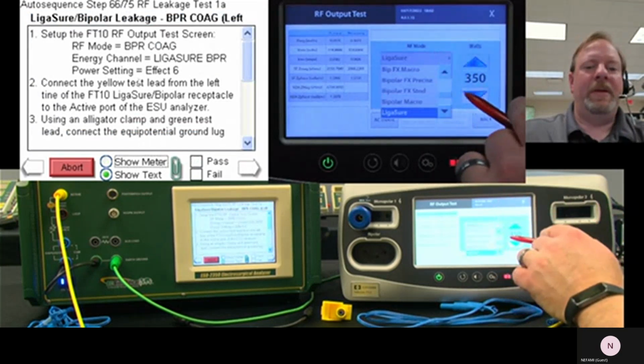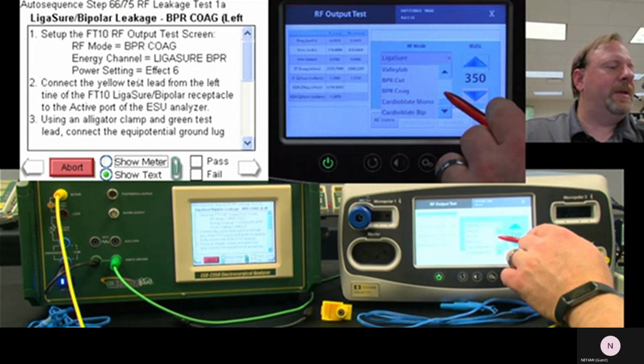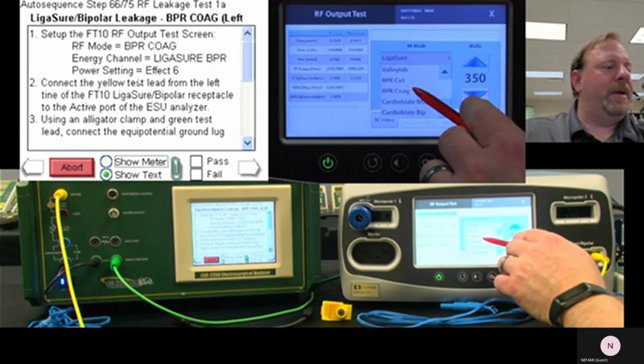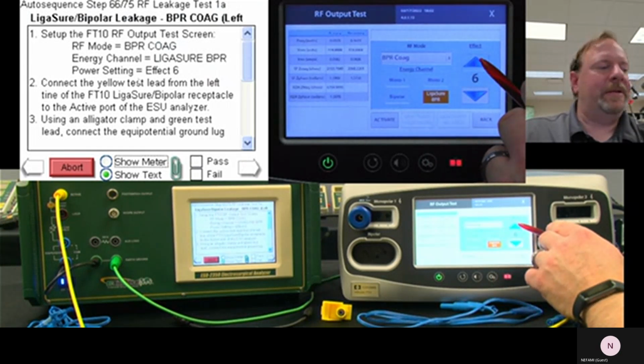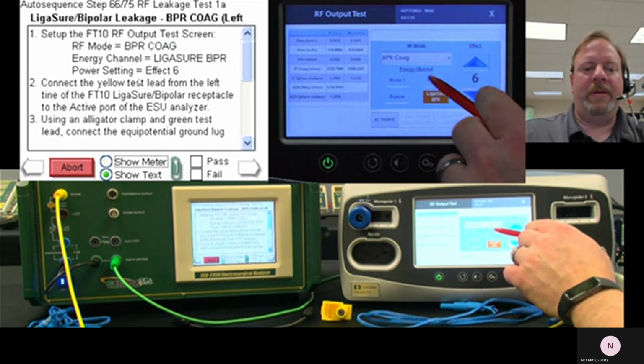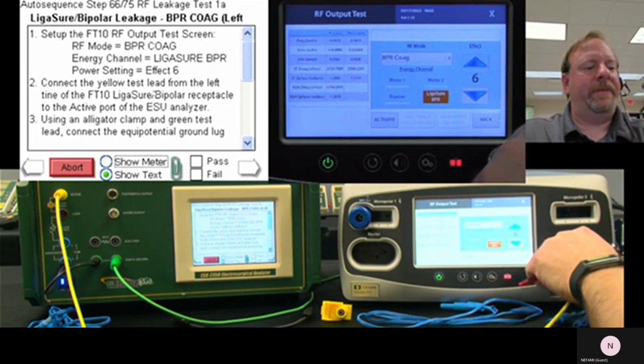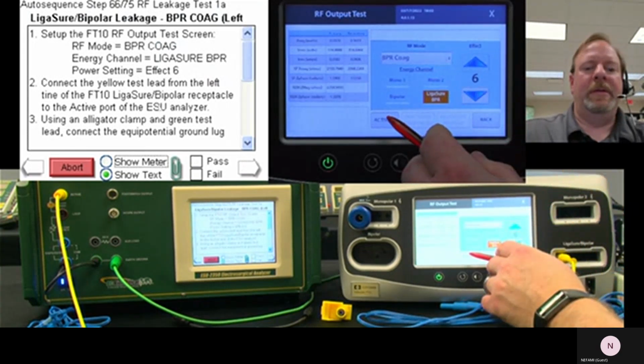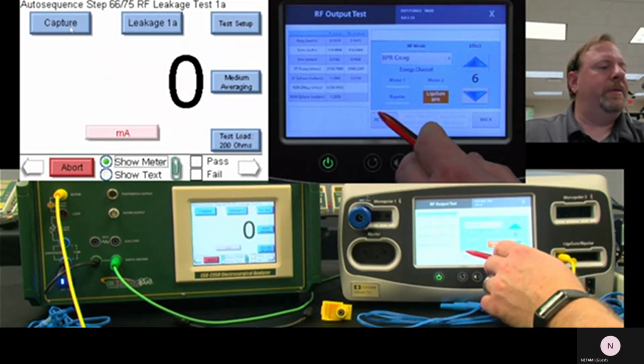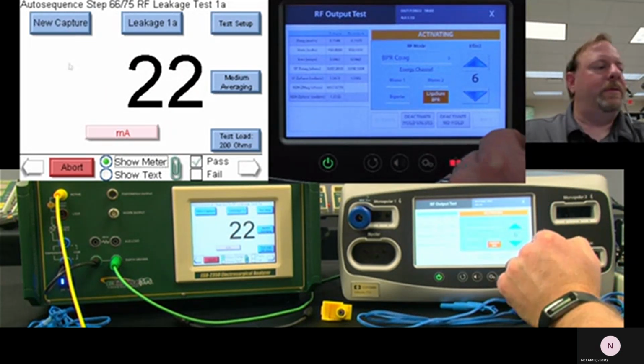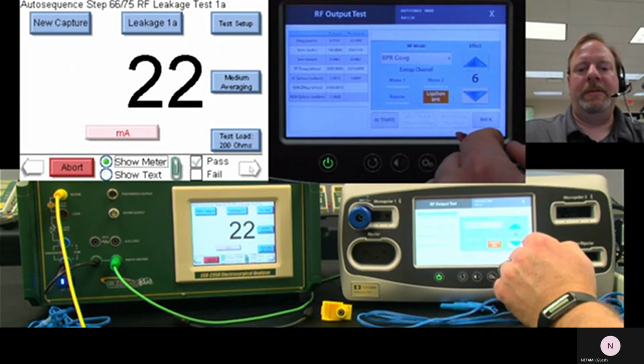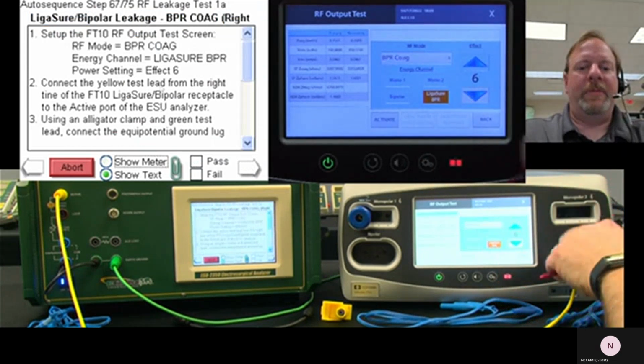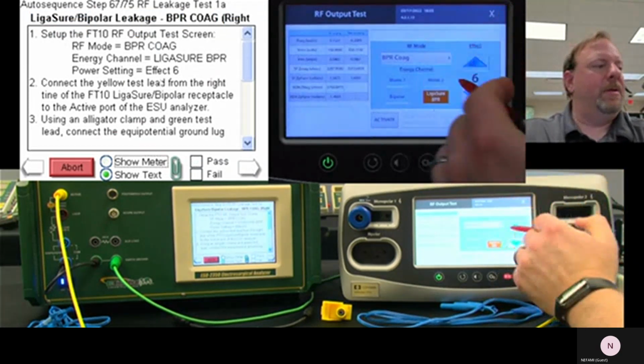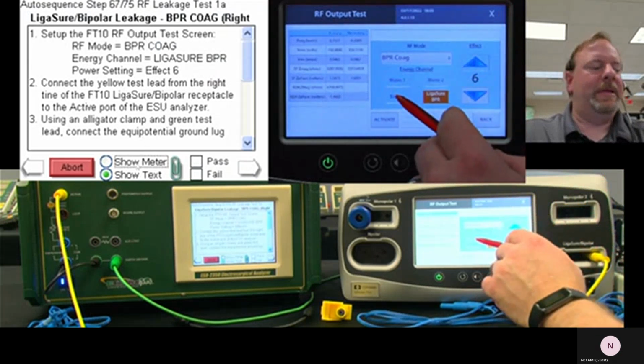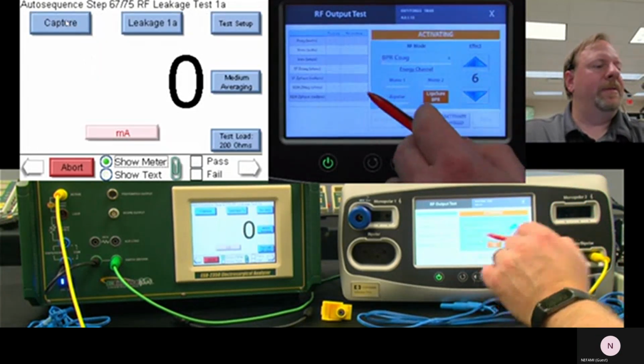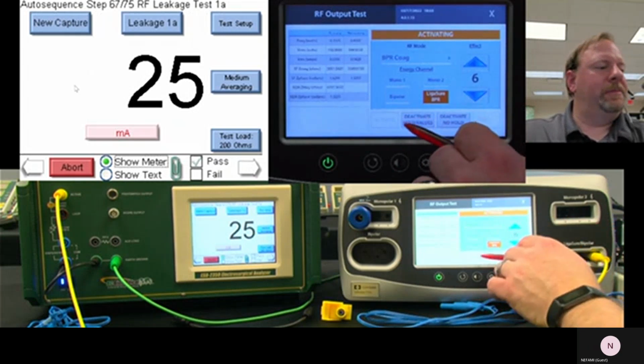And now BPR coag. Yes, the B's are down at the bottom. BPR coag. We'll make sure we get the right setting, 6, the right port. Yellow test lead to the left tine. Go back to the left. Show meter. 22. That's good. And now we're going to go to the right tine. Coag, effect 6. That's the same. Okay.